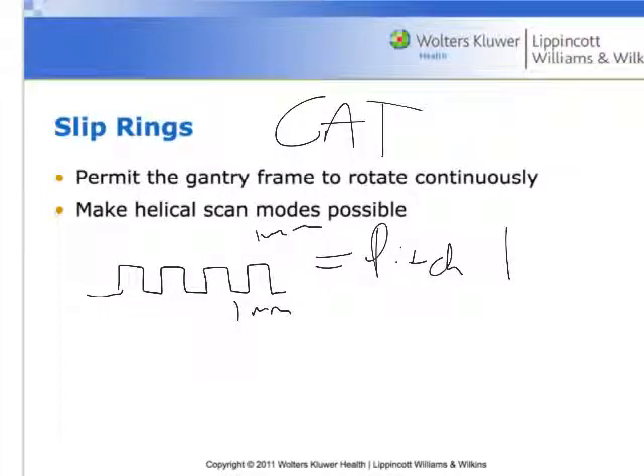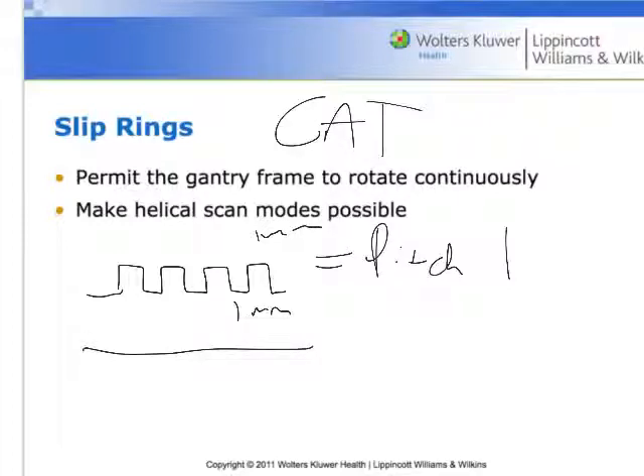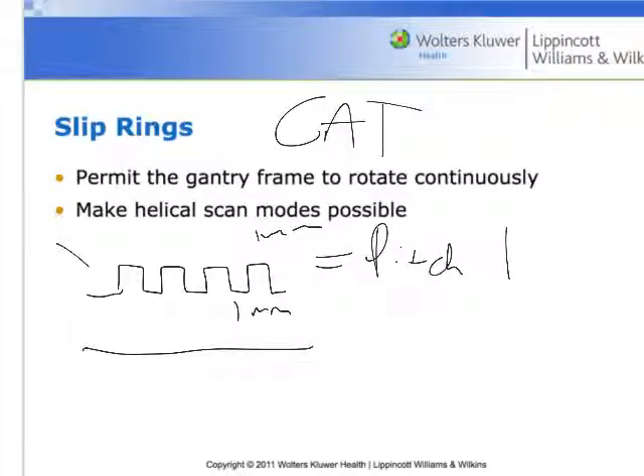Once slip ring technology enters the game, we have the development of helical or volumetric scanning — continuous scanning while moving. On a GE scanner you can see these two different acquisition patterns. Axial looks like the top of a little castle; helical is just moving and scanning simultaneously, all because of slip ring technology.